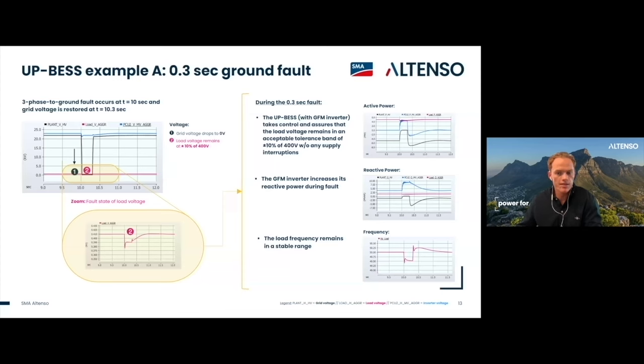The blue line shows the inverter voltage, and the pink line shows the load voltage at the bottom here. In this case, we simulated a 3-phase to ground fault at 10 seconds, and the grid voltage, as you can see, drops to 0. And you can see that the inverter provided an immediate response and increased its reactive and active power to compensate the load voltage and frequency.